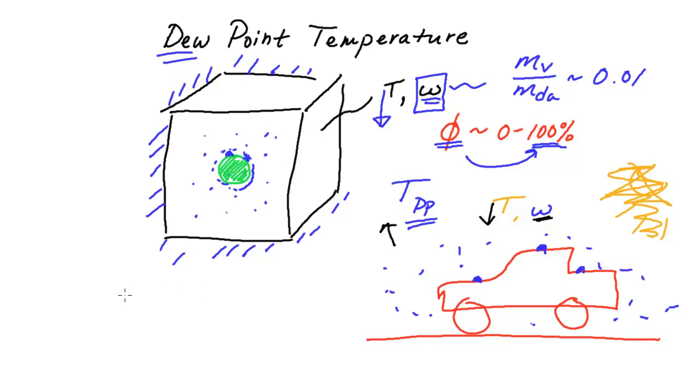And so another key concept that I would like to get across is that the dew point temperature is very literally related to the absolute humidity ratio. So if your current humidity ratio goes up, that dew point temperature goes up. And so there's a direct correlation between these two. You could almost say that the dew point temperature is a function of your current humidity levels. And the same way, you could go the other way.